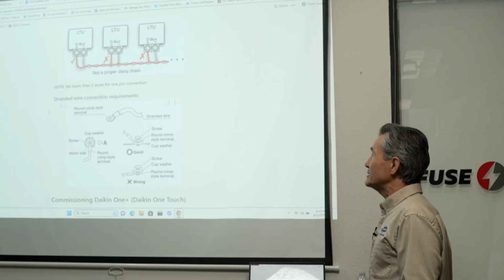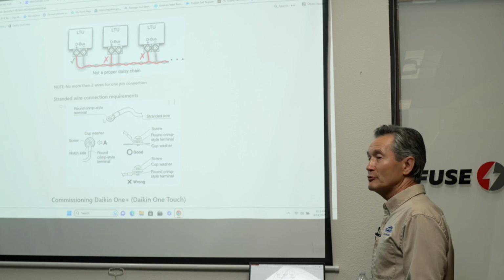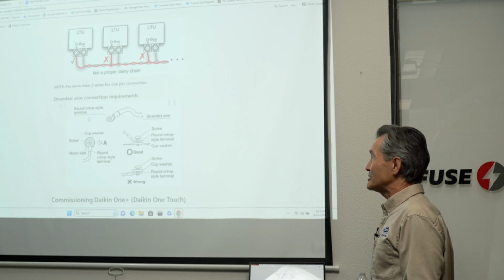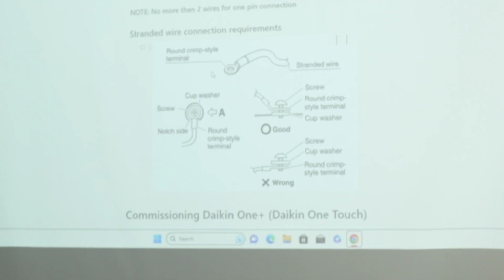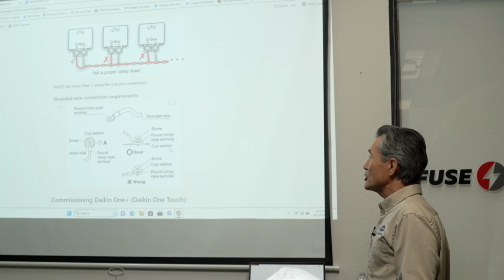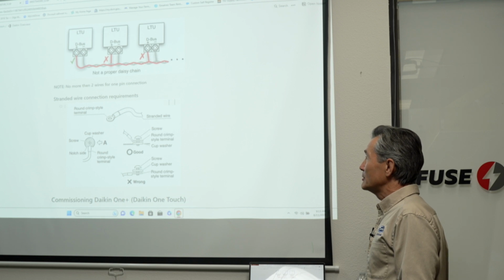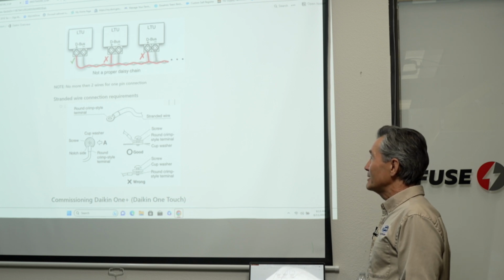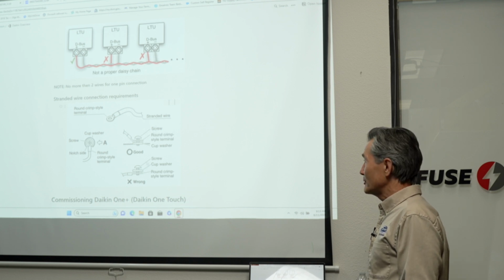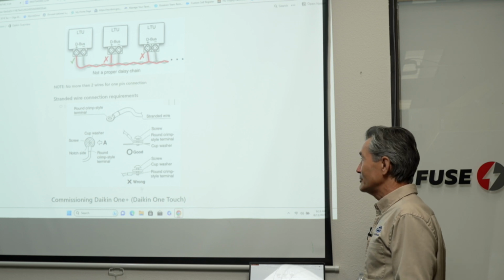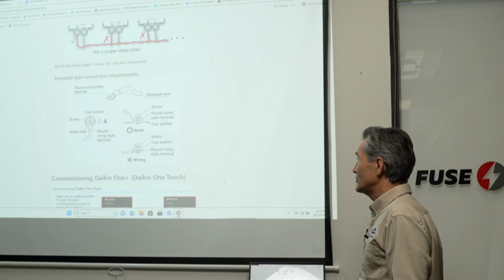This is for stranded wire, so you have to use this type of connection, a crimp style terminal. This mostly applies to grounding. You can't just make a circle and put it together; it has to be done properly. Even the washer should go below the connection, then the screw, not vice versa. It shows what's good and what's wrong, so you have to follow that.